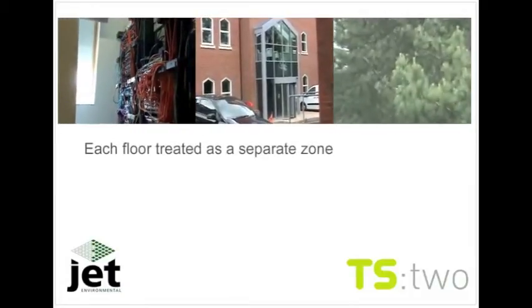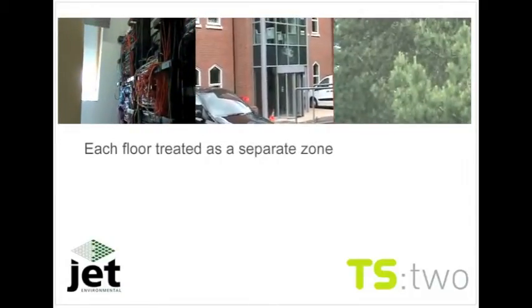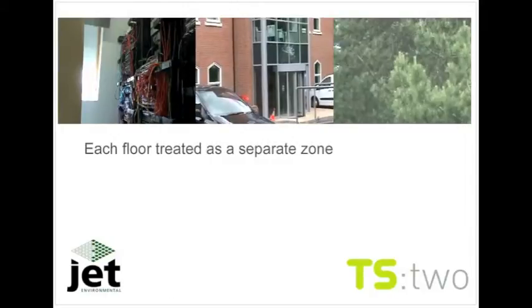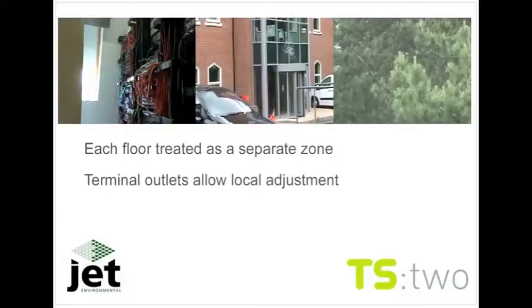Each zone is treated with a dedicated air handling unit incorporating heating and cooling coils. A series of terminal outlets are distributed around the floor void to the offices to allow local temperature adjustment. The zone units monitor the temperature at each of the outlet terminals. The supply air discharge from the local air handling units is based upon the average condition within the zone. The fresh air supply is introduced into the return air path of the zone unit, thereby ensuring that when free cooling is available, this will take priority over secondary mechanical cooling.